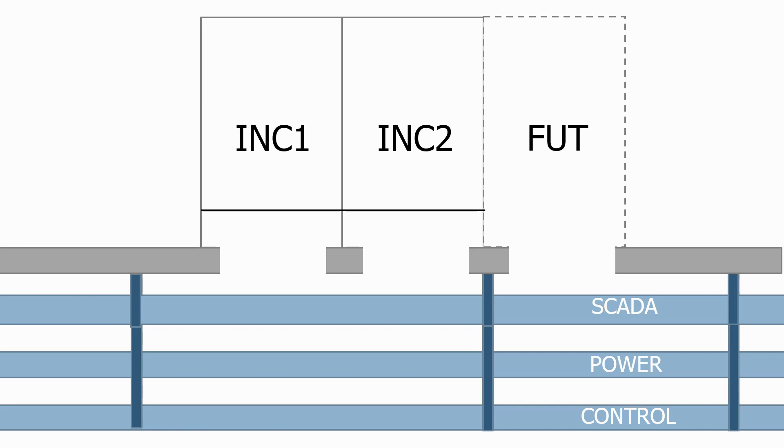The SCADA cables tend to have the lowest bending radius, so it's normal practice to put these on the top layer. We then connect each of the cables onto their associated cable tray.